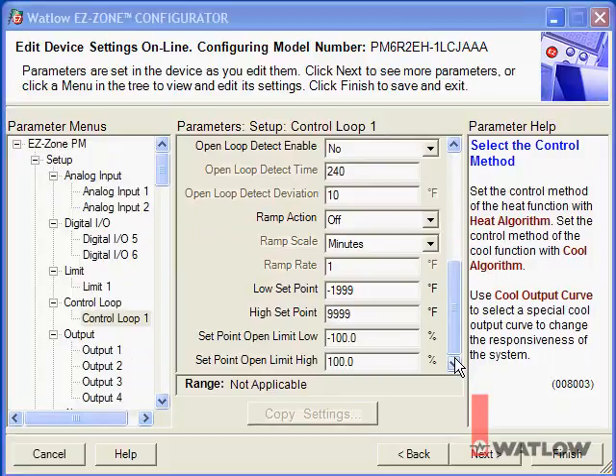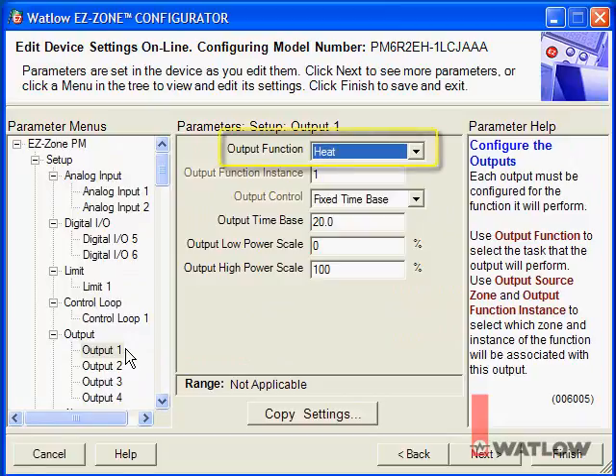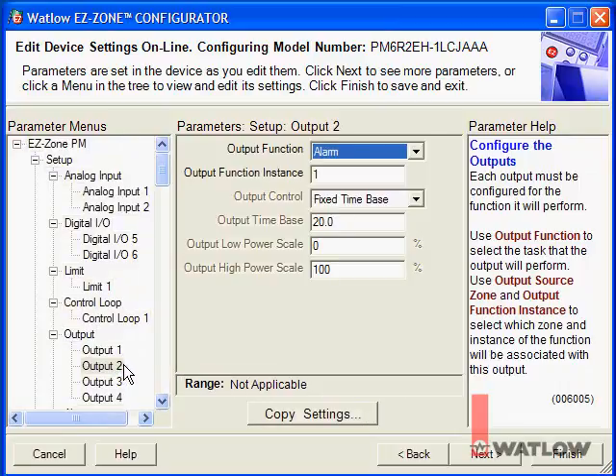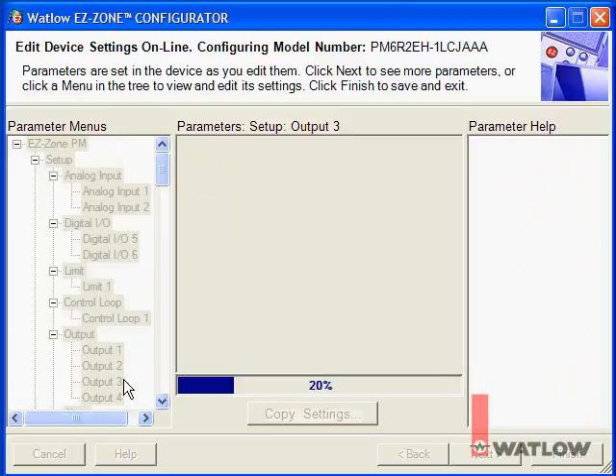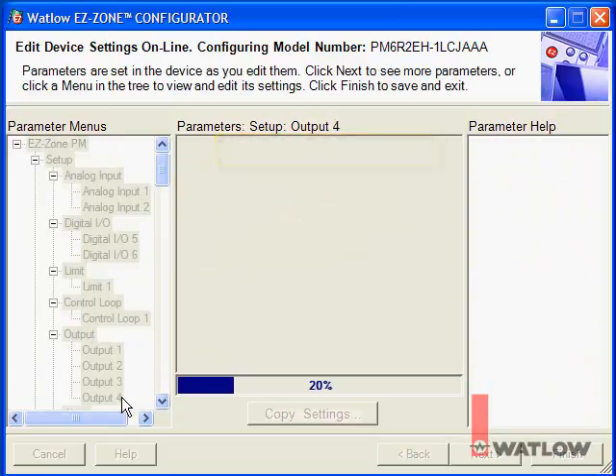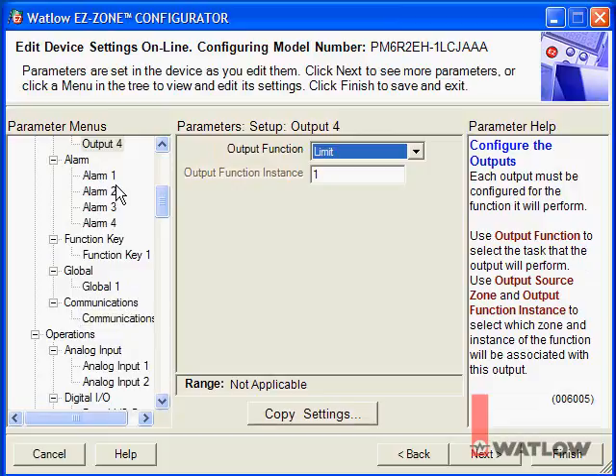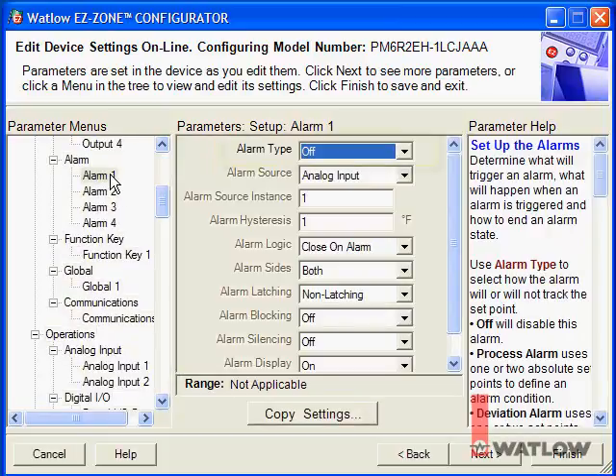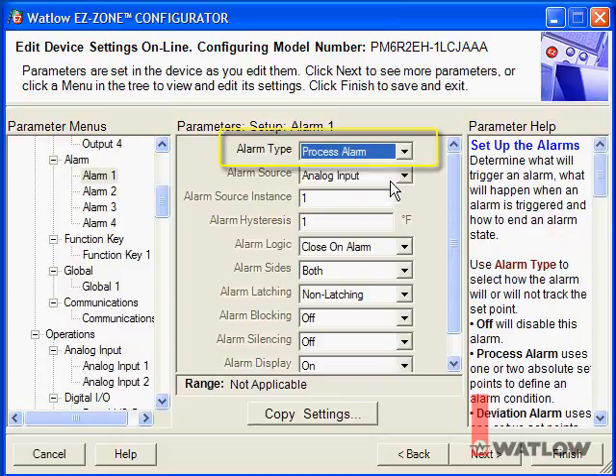We're going to use Output 1 to drive the heater for the control loop, so the default output function setting — Heat — is good. Output 2's default function is as an output for an alarm, and the Output Function instance is already set to 1, so this output is tied to Alarm 1. Output 3 is off. Output 4 is the limit output. To get Alarm 1 to turn on Output 2 when the temperature goes over the high alarm set point, for Alarm Type, choose Process Alarm.